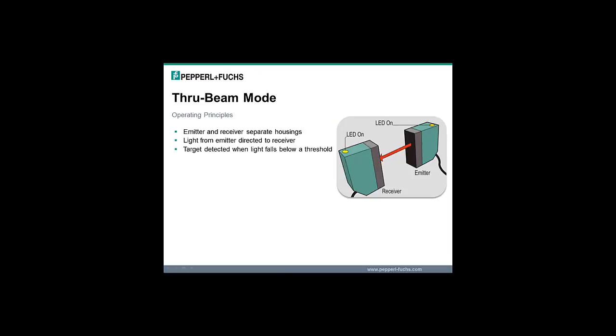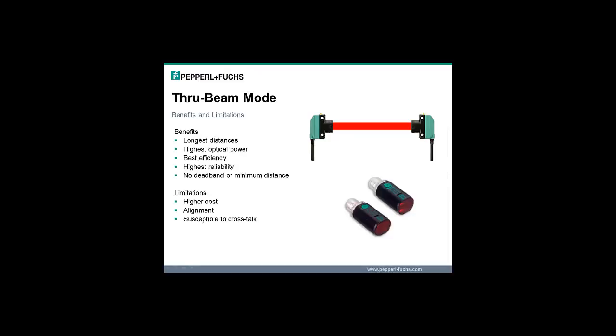The last of the basic sensing modes is the through beam mode sensor. Through beam mode sensors have their emitter and receiver elements contained in separate housings. Light from the emitter is directed to the receiver, and the target is detected when the light at the receiver falls below a specified threshold. Benefits include the longest detection distances, the highest optical power, the best optical efficiency and highest reliability compared to other sensing modes, and no sensor deadband or minimum detection distance.